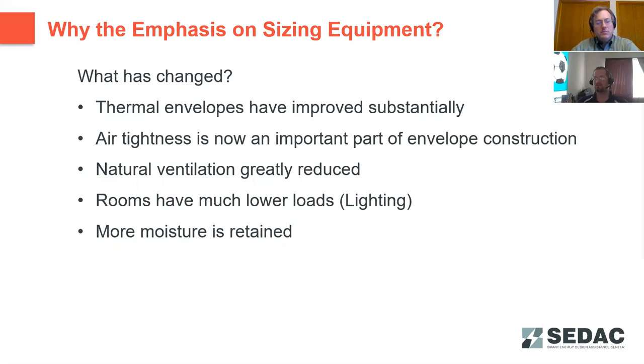As far as when size calculations are required, new construction, obviously. If you're doing an existing remodel where you're completely replacing a furnace or HVAC equipment, it should also be done then. It is in R502 for additions and R503 for alterations. If you're changing the load in the house, you're going to have to do a calculation and match your system to that, potentially, or add a supplementary system to cover that addition. If you're replacing an HVAC system, you are required to do a load calculation on the existing structure and properly size the replacement equipment.